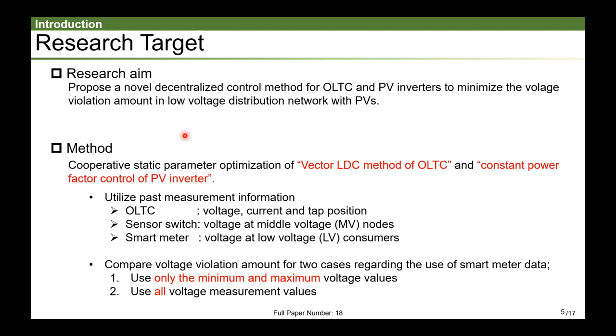In summary, the aim of this study is to propose a novel decentralized control method for OLTC and PV inverters to reduce the voltage violation amounts in the distribution system with PV penetration. Specifically, we propose a static parameter optimization with the vector-LDC method of OLTC and constant power factor control of PV inverter. In this process, real-time information communication is not required because only past measurement information is utilized.